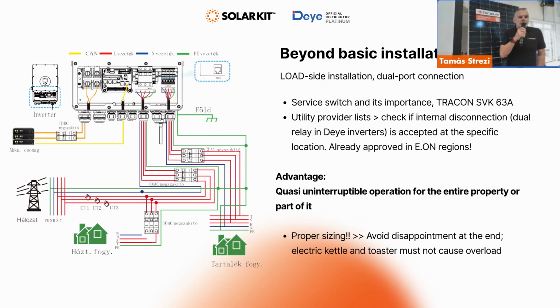So far, I've already talked about the basic installations and a single grid side connection. How you move further from this. Having UPS functionality is a really desirable trait of the Deye inverter. And since it's designed from the ground up as an off-grid inverter, I think this is what it does best. In this case, you are connecting to the load port. The actual installation is really important to keep the safety of your electricity systems. It's also dependent on the regulations of your distribution network operator, whether this is actually allowed or not.